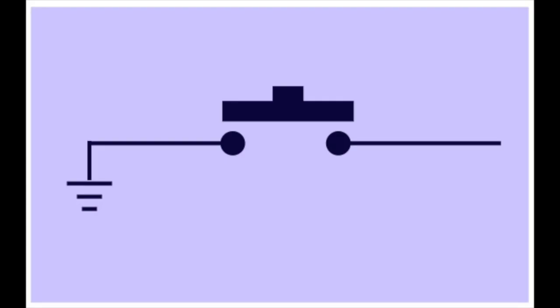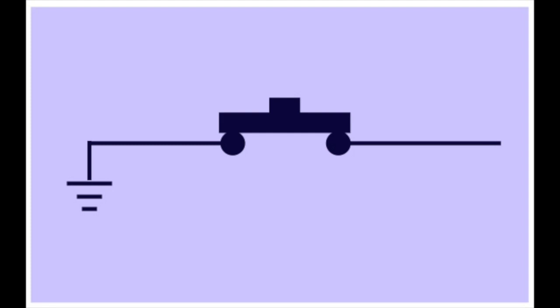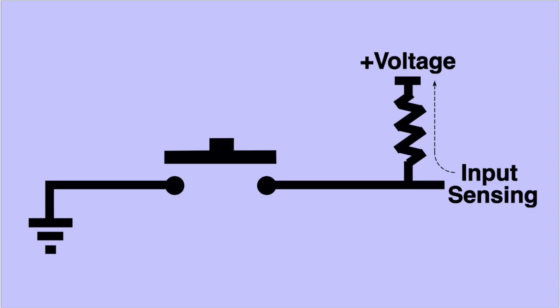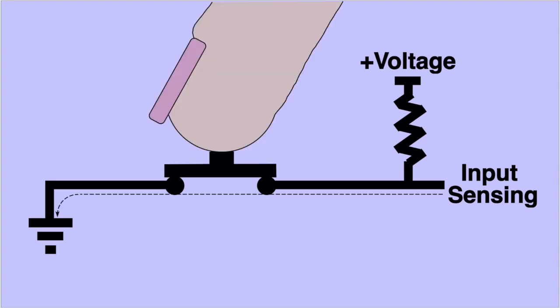Generally, a push button connects to ground when pressed, or when the internal contacts are closed. Connecting the wire to ground sends that ground signal back down the wire to the receiving device, whatever it may be. How does the device see the ground? Well, inputs generally have a pull-up resistor connected to the plus voltage and monitored. If there is no connection on the input, the input sees that plus voltage or a high with a small current through the pull-up resistor and waits. The moment someone presses that button, the contact closes and the wire now connects to ground through much less resistance than the pull-up resistor. The input now sees the low and tells the device that the input has been activated.